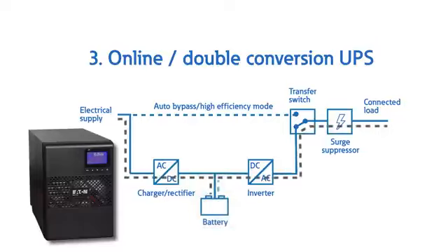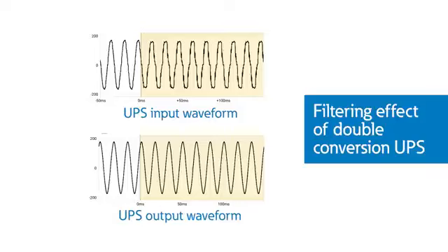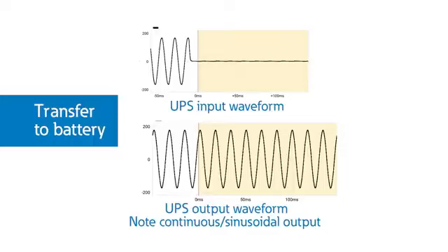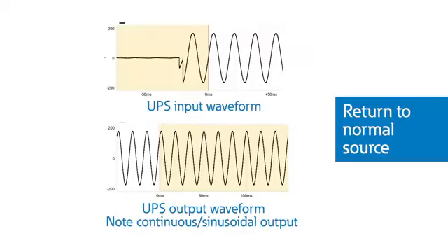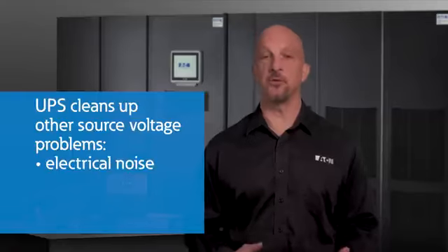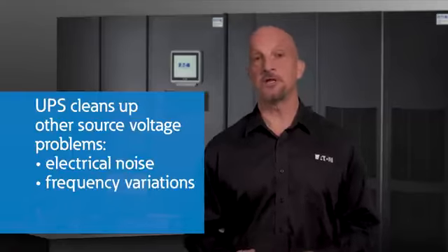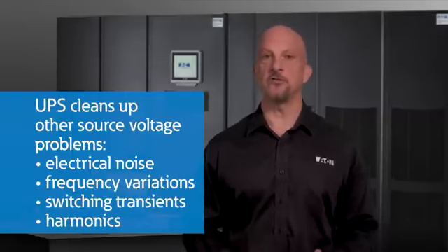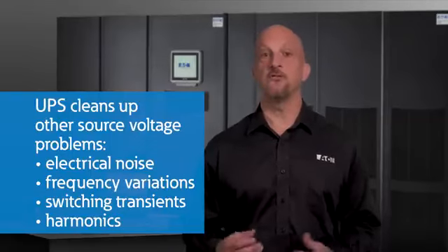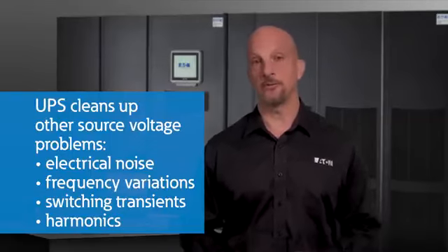The input and output voltages are completely isolated from each other, allowing the UPS to clean the voltage for the load and will not disrupt the power during the transition to the battery or the transition back from the battery. This UPS can clean up other problems with the source voltage like electrical noise, frequency variations, switching transients, and harmonics because it's always in the circuit feeding the load through the rectifier and inverter.